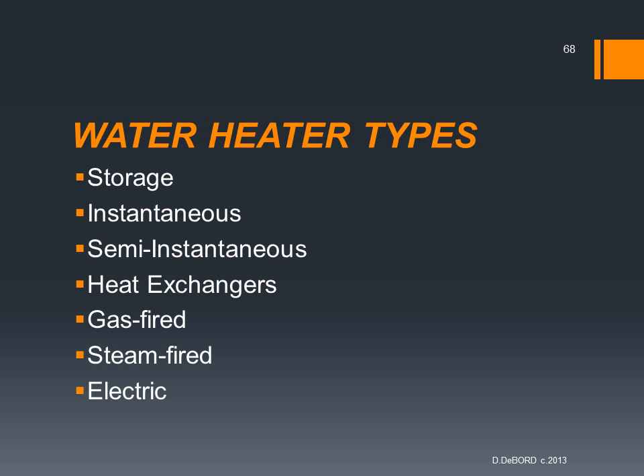That's one of the most common problems that we have with water heaters: combustion air and the flue. If you specify a water heater and then the contractor installs a different water heater, even if it's the same BTUs, it might not have the same air and exhaust requirements. All this has to be coordinated carefully, and if it's changed, we need to make sure that it works.